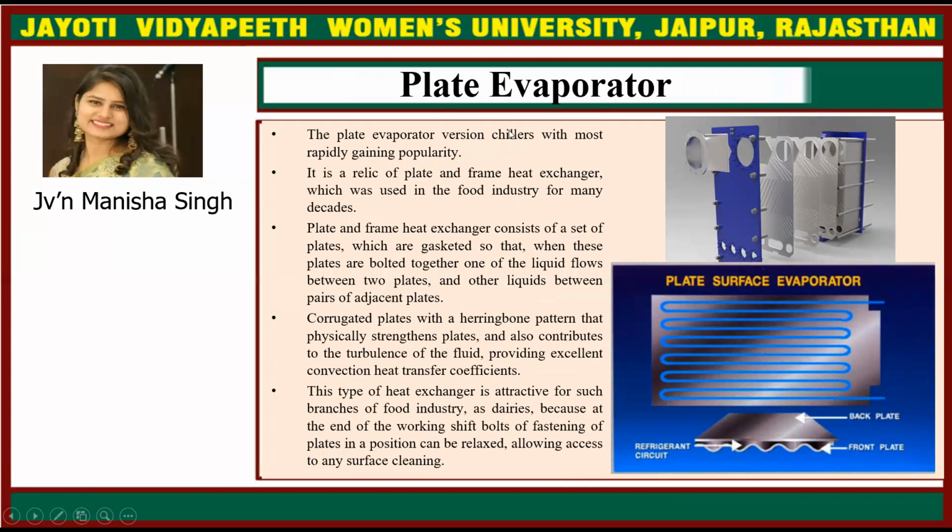Another type of evaporator is the plate evaporator. The plate evaporator is rapidly gaining popularity. It is a relative of the plate and frame heat exchanger, which was used in the food industry for many decades. A plate and frame heat exchanger consists of a set of plates which are gasketed so that when these plates are bolted together, one of the liquids flows between two plates and the other liquid between pairs of adjacent plates.